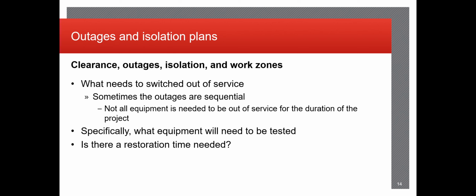So we're going to get into the outage and isolation plans. We need to identify for an outage what needs to be switched out of service. And what this means is when you take an outage at a substation, the client does not want to open up all the equipment and make the whole yard dead. Usually that involves them losing a lot of money, a lot of customers, and you're going to be putting more load also on other stations, other transmission lines, other distribution lines, etc., etc.